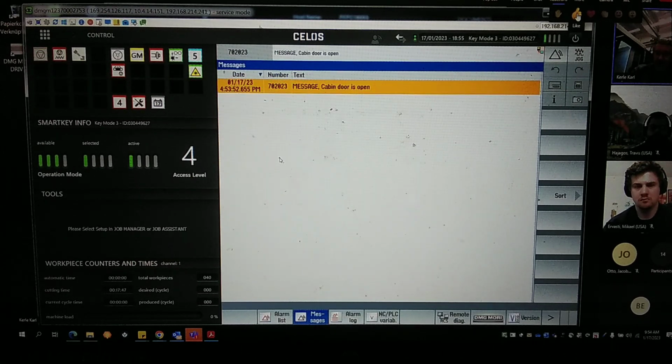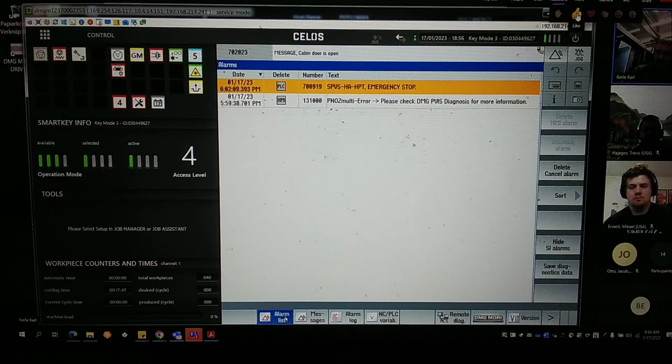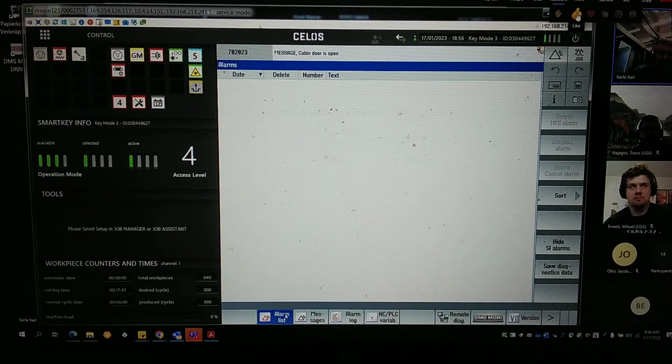So now here in the message window appears the message emergency stop is pressed, or response of machine power on 0. And by the alarm, nothing is indicated there. Why? These messages appear fully automatically. That means here we have a dynamic initialization. If a reason occurs, you see an alarm or a message until the reason disappears, then the message is gone here. Okay?